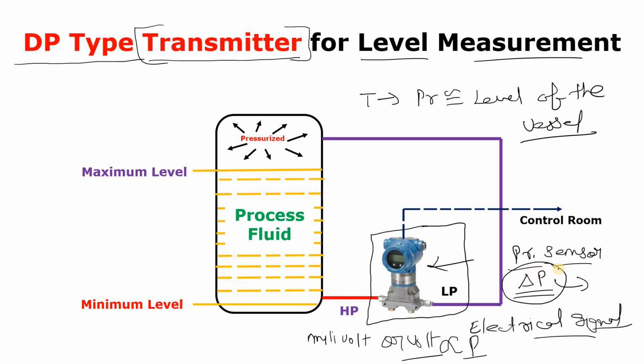Got my point? I have the pressure sensor, which will convert the measured pressure into other parameters like millivolts, capacitance, resistance, depending on the type of sensor we are using within that DP type transmitter. Generally the Wheatstone bridge converts the resistance or capacitance, which is the output of the pressure sensor, into an electrical signal. It may be in the form of millivolt or volt. That millivolt or volt is proportional to the pressure, and then the transmitter will convert it into the pressure, and this pressure will be equivalent to the level. We can say it is the level signal.